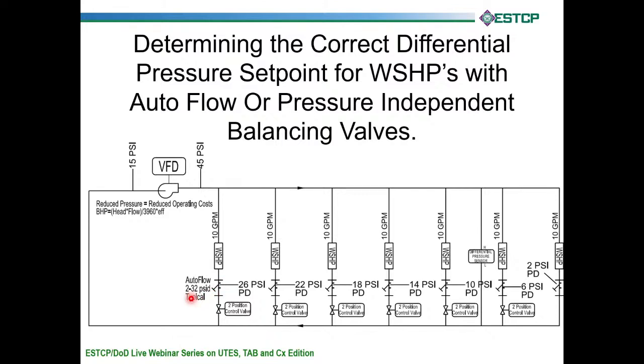and if your differential pressure is anywhere between 2 and 32 psid, those numbers can vary a little bit per manufacturer, per valve, but on the valves that we use a lot, 2 to 32 psid, you know that you have 10 gallons a minute. So in a sense, the system is self-balancing. However, you still need a TAB contractor to go through here and verify that you're not out of range. If you are out of range, then the pump is either running too fast or too slow. So pretend the TAB contractor comes through here and he measures everything, and everything is 2 to 32. But this very remote valve out here, the one that's farthest away from the pump, is, instead of 2 psi, pretend it's 5 psi. In that case, your pump is running too fast.